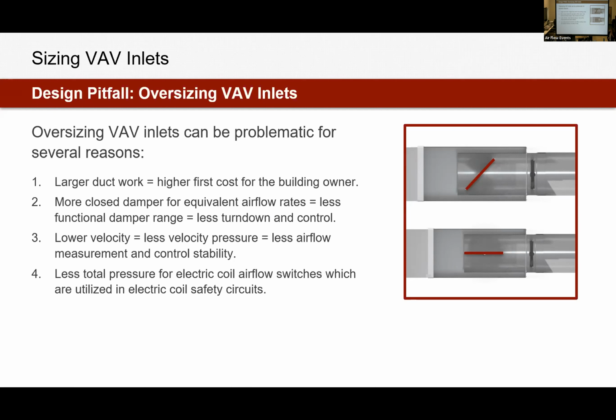If we were to jump to a 10-inch box, our damper is now going to have to maintain a more closed off position. We've got a larger valve with the same amount of airflow going through it. So we have to modulate that damper back to really control down to that airflow. When we're sitting in a closed off position, like that top picture there, we have less range and less controllability, less turn down. It's just a little bit tighter of a range we're trying to control to, which is more difficult.